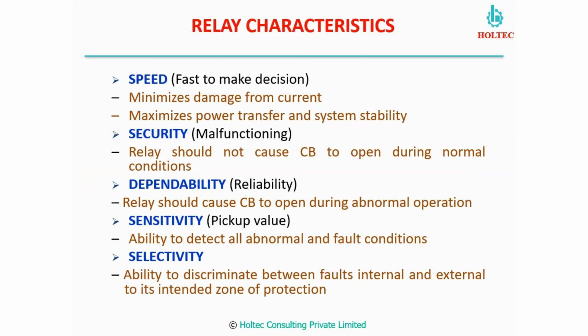Then the next characteristic is security. Security means malfunctioning should not be there in the relay. That means it should not open the switchgear, or initiate the tripping, during normal conditions. Then the third one is dependability or reliability. It means in any abnormal condition, it should be ensured that the relay should cause the system to disconnect. Then sensitivity means ability to detect all abnormal or fault conditions.